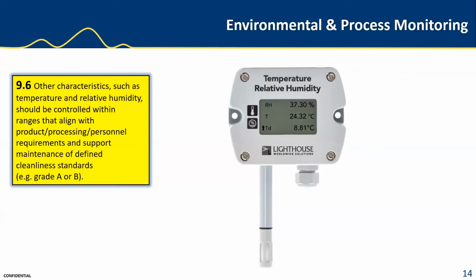So here's a fun thing to consider. What if you were using one sensor and that sensor drifted? How would you know, if you have one sensor? BMS sensors are not routinely calibrated, so that drift could go on unnoticed. But if you had an independent sensor monitoring the same location, that drift would be caught pretty quickly. So overall, room temperature should remain at ambient for personnel comfort. Anything above 25 degrees Celsius and with some moisture in the room could enable a suitable breeding ground for viable particulates. So again, that's just an example of the drift in electronic sensors, and not having an independent one to watch. You may not actually see that drift happen.